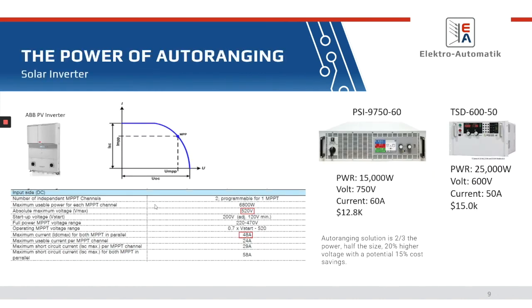What you'll see here is just a typical ABB PV inverter. The PV inverter is rated for 6,800 watts. The maximum voltage into it is 520, but the startup voltage is actually 200 volts. So again, you have this wide operating condition. And maximum current at the maximum power point at startup is going to be, say, 48 amps.